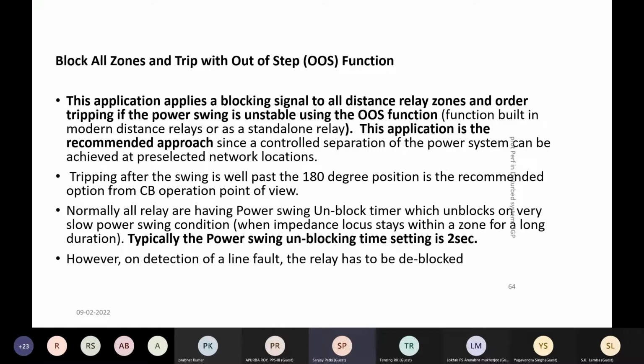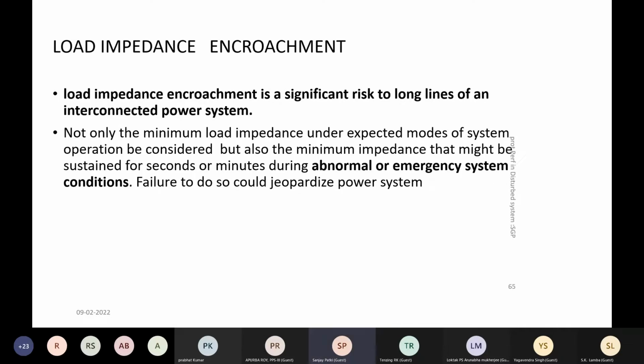In the northern region, actually, the Regional Power Committee of Northern Region, they have already given instructions to adopt blocking of all the zones and tripping of the same line by out of step protection. So this has been already done partly. Other regions, I'm not aware of this thing, but this is the general recommendation. The second thing is how do we ensure that lines do not trip in an undesirable manner during power swing or load swing phenomena.